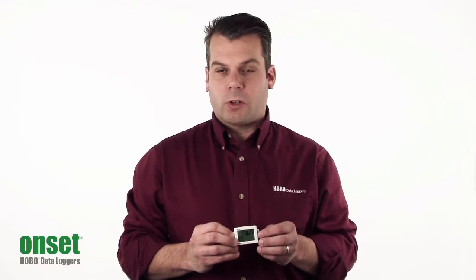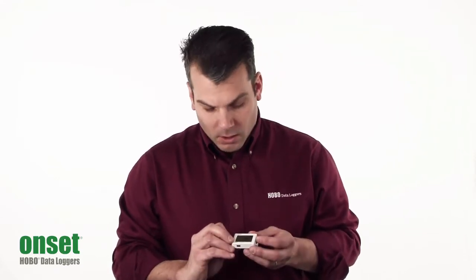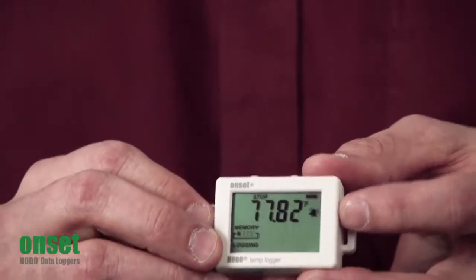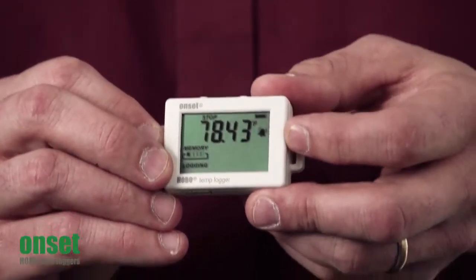And we have another mode called burst logging, where you can record above or below a particular threshold at a faster sampling rate. Also, as you can see, we have visual alarms, so if something goes outside of range, you can be alerted.